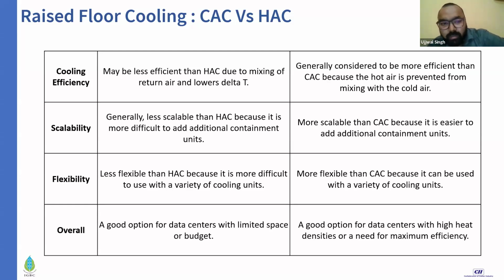So as I said, both options have their pros and cons. To summarize the general decision-making: if you have a very large hall, it's suggested to go for cold aisle containment. If you have very small halls, or partitioned halls with airtight partitions, in those scenarios hot aisle containment may suit you better.